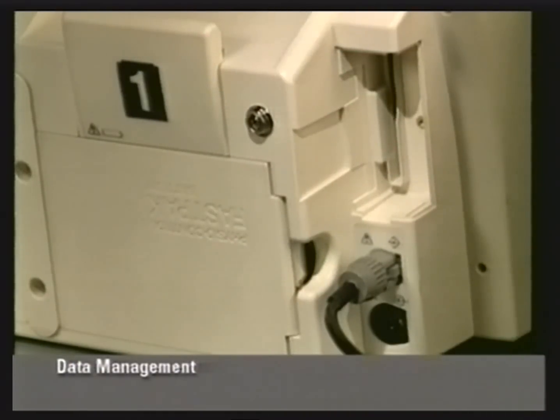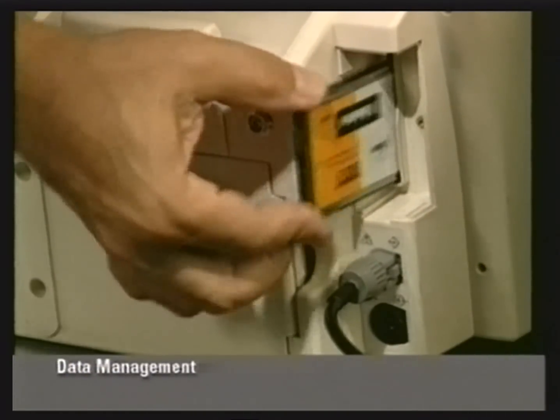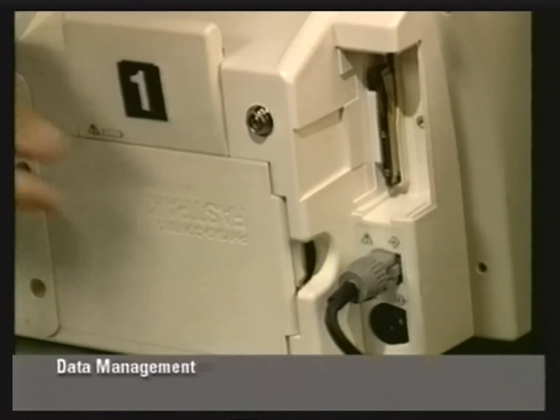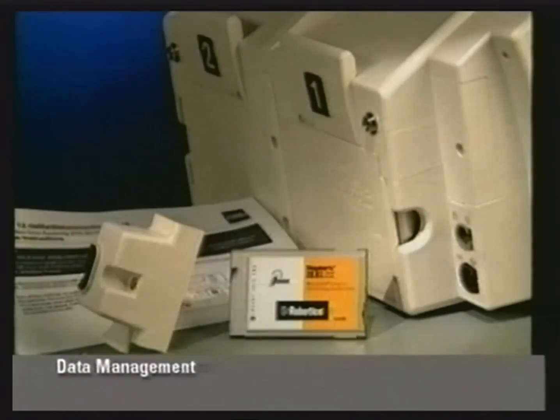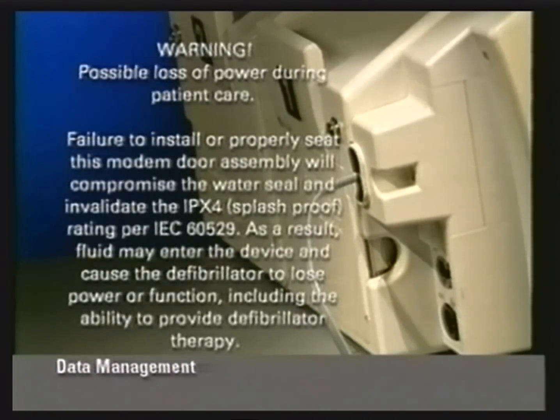The PC card modem installs into the PC card slot on the back of the defibrillator. Using an internal PC card modem requires installation of the modem and the modem door assembly, which allows access to the phone cable and helps prevent fluids from entering the device. Failure to install or properly seat the modem door assembly will compromise the water seal rating of the Lifepak 12 defibrillator monitor. As a result, fluid may enter the device and cause the defibrillator to lose power or function, including the ability to provide defibrillator therapy.